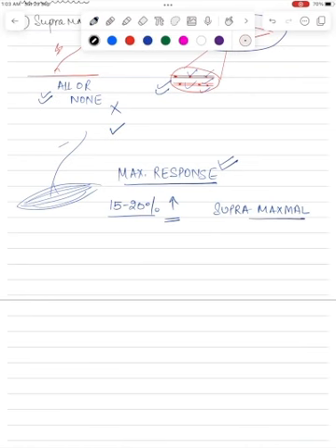The second term I would like you to be familiar with is calibration. Calibration of a device used for objective neuromuscular monitoring is essential to ensure that the observed response to the supramaximal stimulus is within the measurement window of the device, and it is as close as possible to the 100% of the control value.